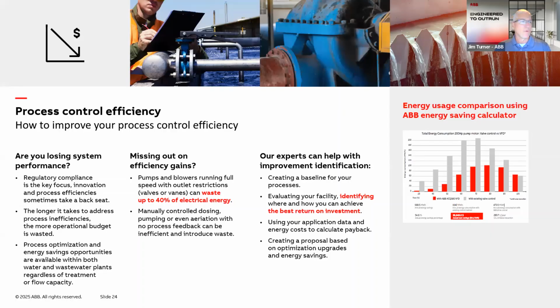So if Courtney would have presented first, and when she comes back on, you're going to hear that she talks about some really excellent opportunities to save energy by applying super premium efficient motors to all applications. But there's even more savings that can be found by applying VFDs to pumps and systems that rely on throttling valves to control flow and pressure. Replacing a throttling valve with a VFD can typically save enough energy to pay back that investment within about 18 months, if not sooner. We have an online calculation tool.